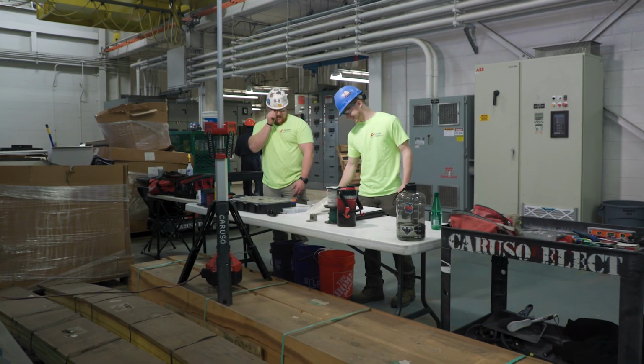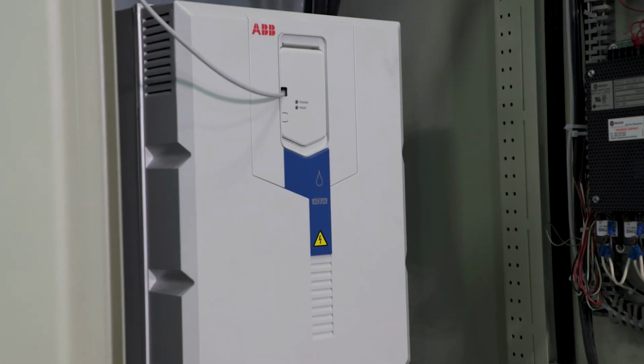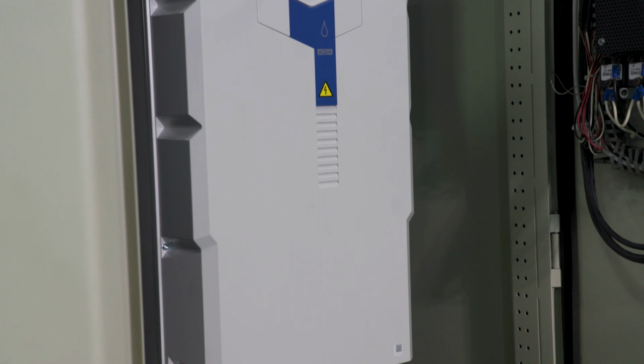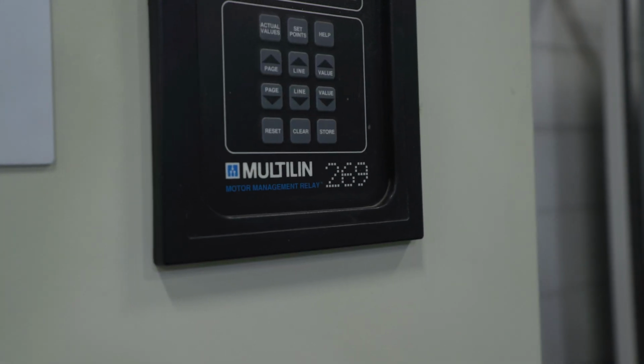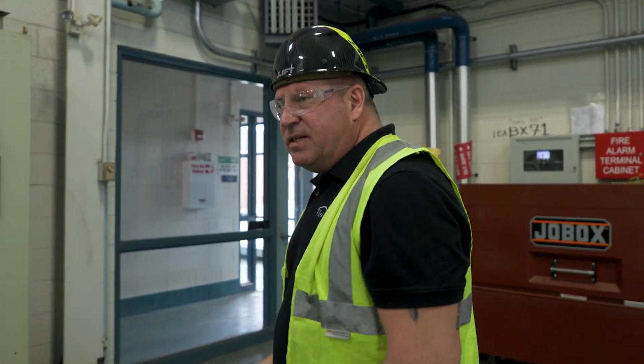There was a separate box here for it, so we're gutting the box, putting a new one in there, and then we're putting a new VFD in, integrating to the old controls, which is just control wiring, and then we test them when we're done and make sure it works through their SCADA system. And now we're going to program it and test the pump.